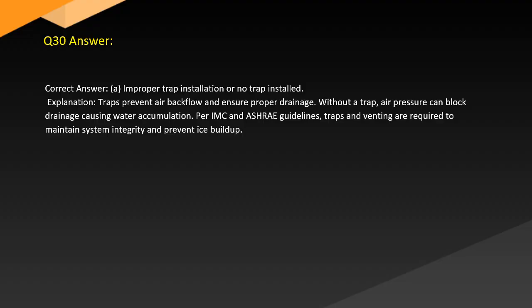Answer. Correct answer: A. Improper trap installation or no trap installed. Explanation: traps prevent air backflow and ensure proper drainage. Without a trap, air pressure can block drainage, causing water accumulation. Per IMC and ASHRAE guidelines, traps and venting are required to maintain system integrity and prevent ice buildup.